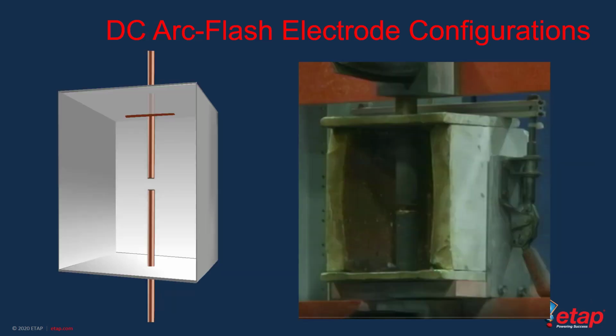However, a very common test used in laboratory conditions for high current DC arc flash tests is the butted electrode configuration. The fact that the electrode gaps can be easily adjusted or controlled makes this a very preferable configuration for single phase AC and also DC arc flash tests. As we will see in the next few slides and videos, there may be some additional considerations which need to be applied when using this butted electrode configuration. However, that is really not the focus of the current discussion. We are trying to see how higher arc current DC arcs produce significant amounts of incident energy, and how the calculation methods available in ETAP can help us to calculate more accurate results.